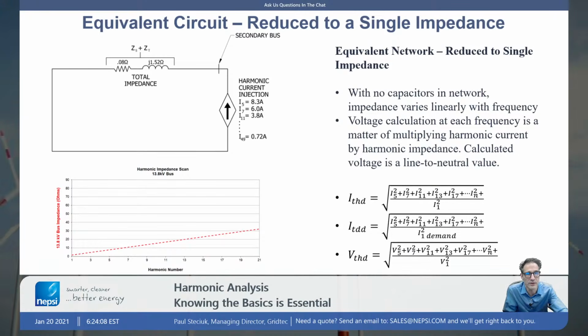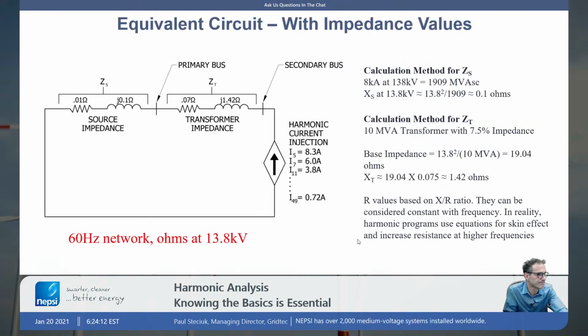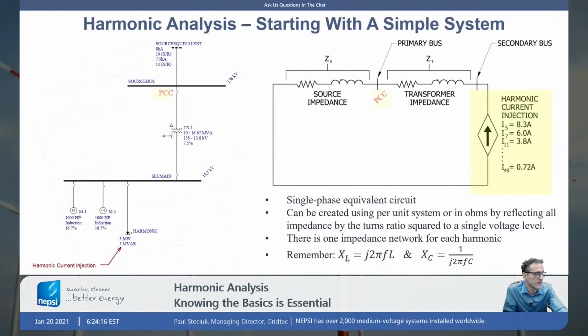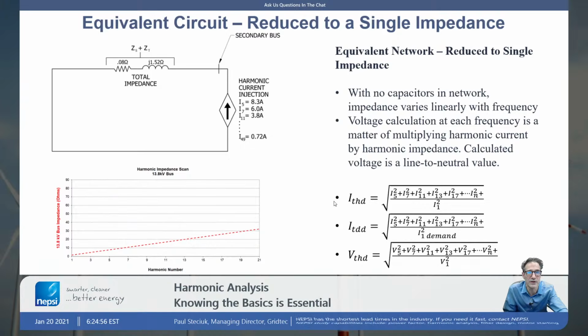Remember, going back to the previous slide, I didn't take note of it. Here, X of L, the inductive reactance, is equal to 2 pi f L. So if I go up in frequency, say to the fifth harmonic, I've got to multiply my fundamental frequency impedance, or X of L at the fundamental frequency, by a factor of 5 because it's at the fifth harmonic. Capacitors, on the other hand, as you go up in frequency, the impedance drops. All right, so you take the 60 or 50 hertz reactance and divide by 5 if it's a capacitor bank. So it's easy to develop the impedance model for each and every frequency, and that's what we do there.